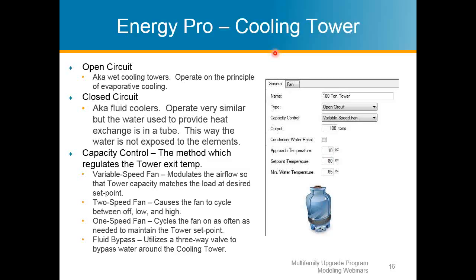And then you have different kinds of capacity controls. So like I said, you have the variable speed, which modulates the airflow so the tower capacity matches the load at the set point. So that's your fan, that large impeller fan. Two-speed fans cause the fan to cycle between off, low, and high. And you can have your one-speed fan to maintain the tower set points. So you have a one-speed fan that's maintaining that tower set point for temperature.